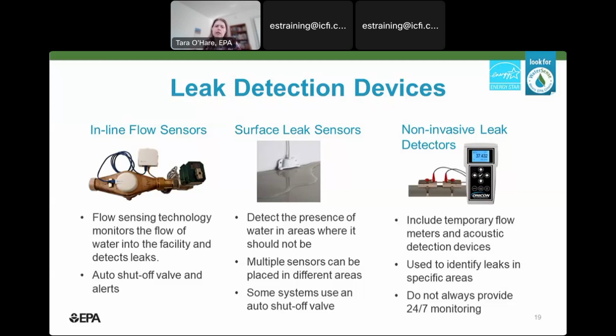There's also non-invasive leak detectors, and these are temporary flow meters and acoustic detection devices. An acoustic detection device is one that uses sound waves to determine how much water is going past that particular part of the pipe. They're used to identify leaks in specific areas, but they don't always provide 24/7 monitoring. But they can be moved around. You just strap it onto the outside of the pipe and let it run. And it can be moved to a different location throughout your facility whenever you want to. So it can be a good option if you want to spot check things, like a couple of restrooms, or you want to look at your cooling tower. It can be really helpful that way.